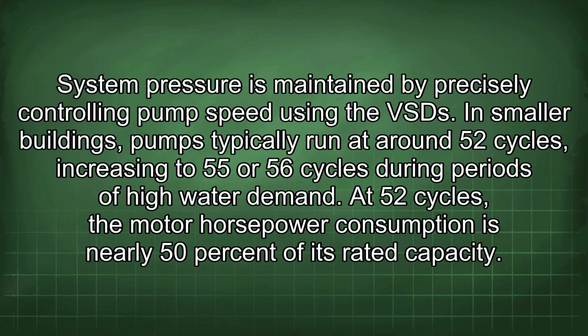realistic. System pressure is maintained by precisely controlling pump speed using the VSD. In smaller buildings, pumps typically run at around 52 cycles, increasing to 55 or 56 cycles during periods of high water demand. At 52 cycles, the motor horsepower consumption is nearly 50% of its rated capacity.